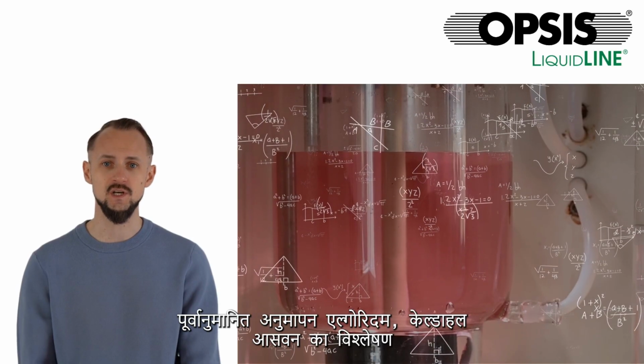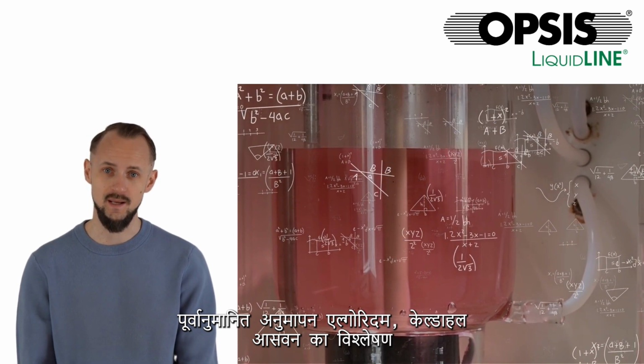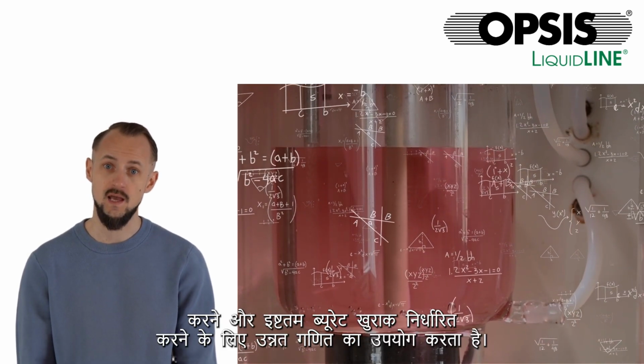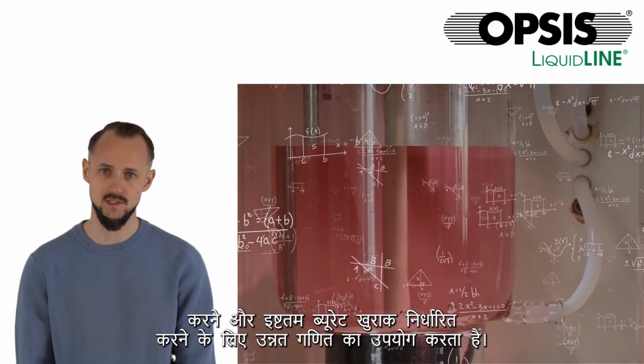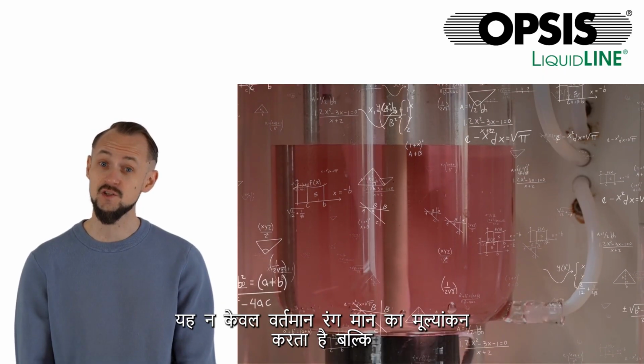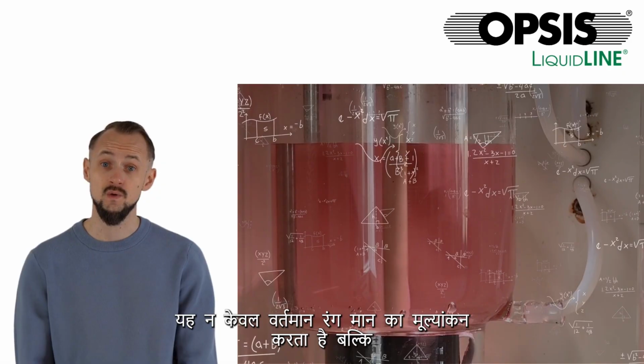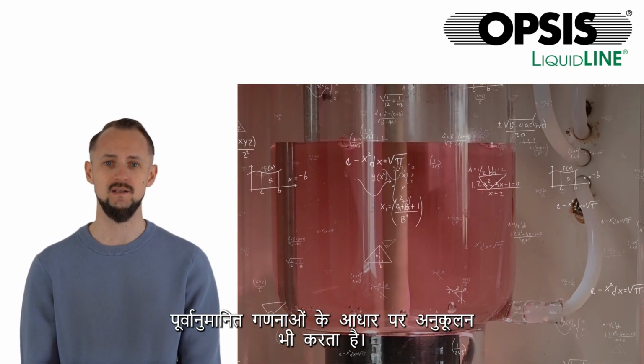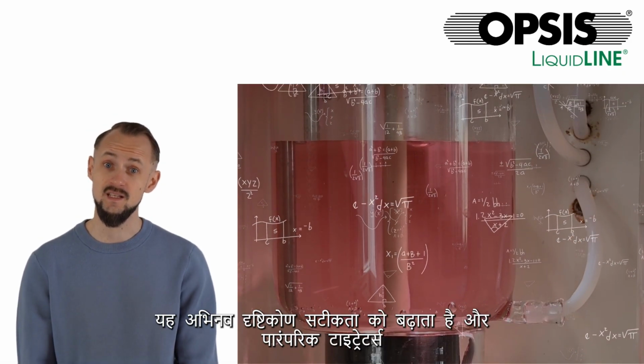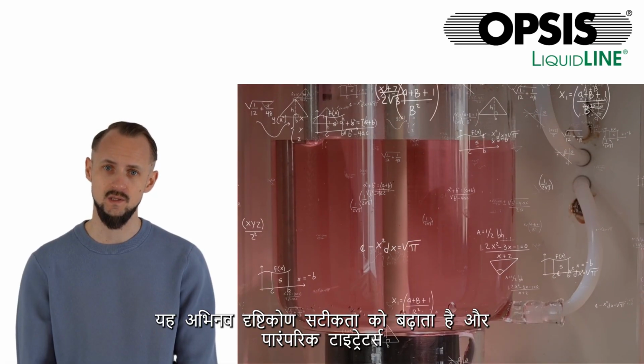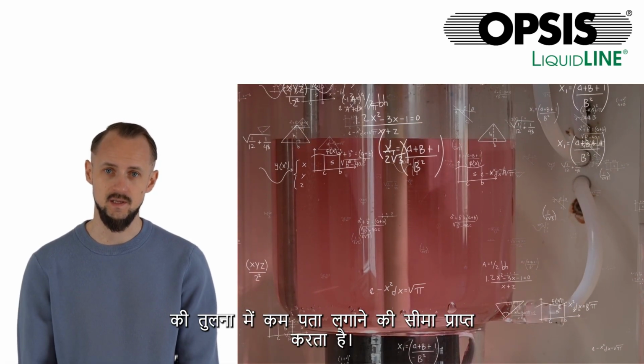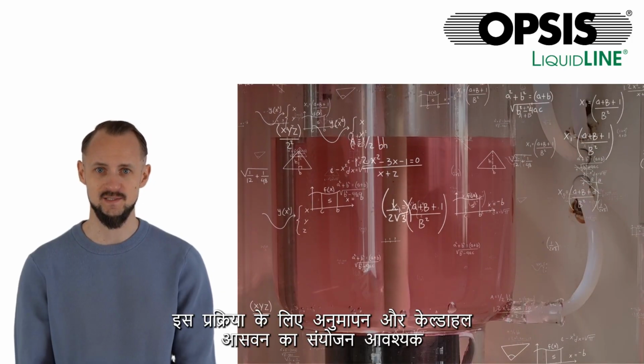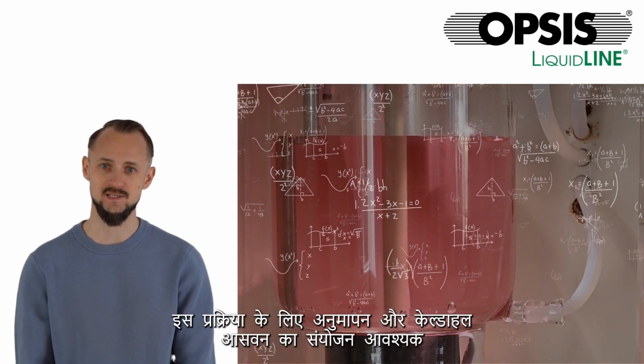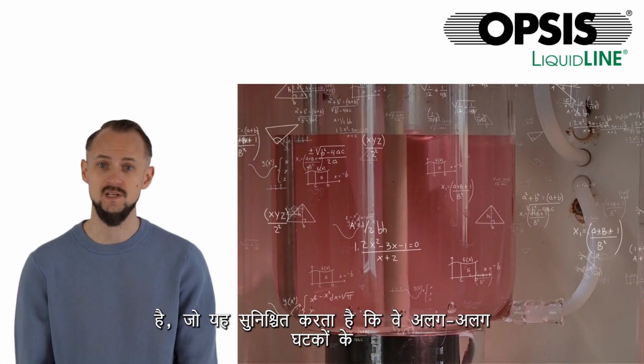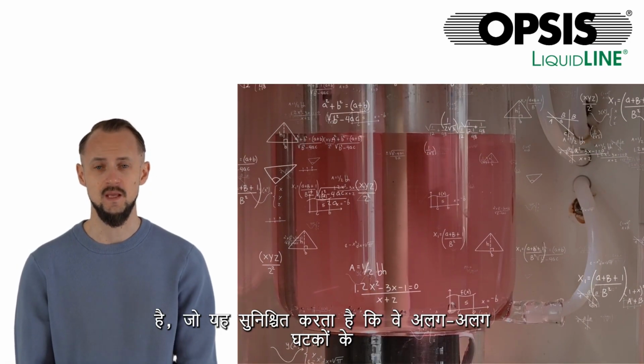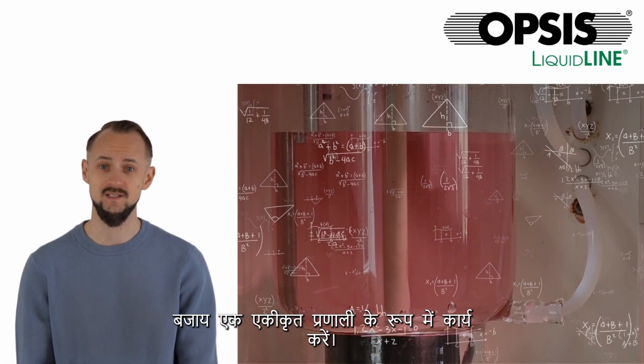The predictive titration algorithm employs advanced mathematics to analyze Kjeldahl distillation and determine optimal burette dosing. It evaluates not just the current color value, but also adapts based on predictive calculations. This innovative approach enhances precision and achieves lower detection limits compared to conventional titrators.